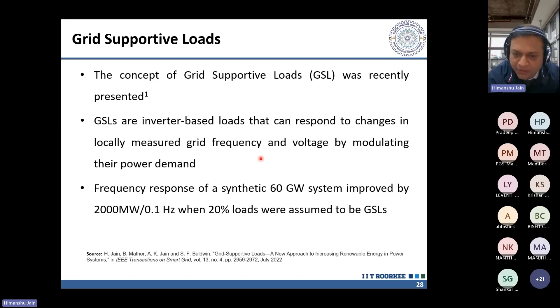So what does that all mean? What it really means is that, like a generator which has droop control, a governor, we would add a governor to these loads as well. Each inverter has a maximum and minimum current. We will limit it to that. And then we can decide for how much time we want to provide this kind of support. As I said, frequency response in this time frame is like 20, 30, 40 seconds, not more than that.